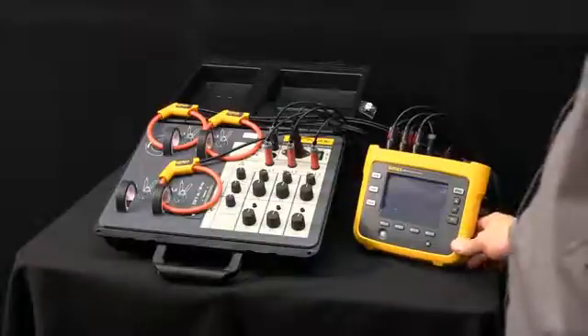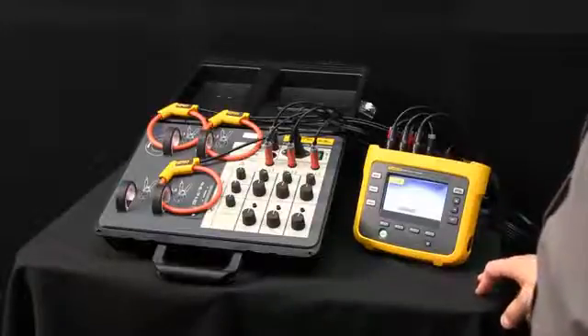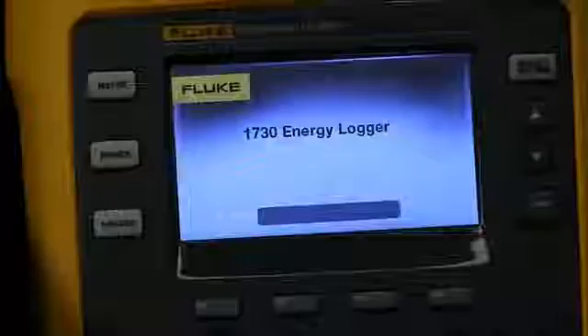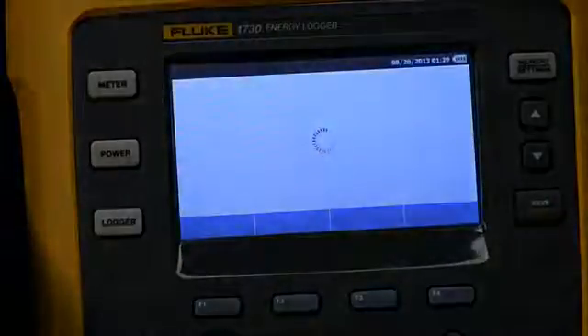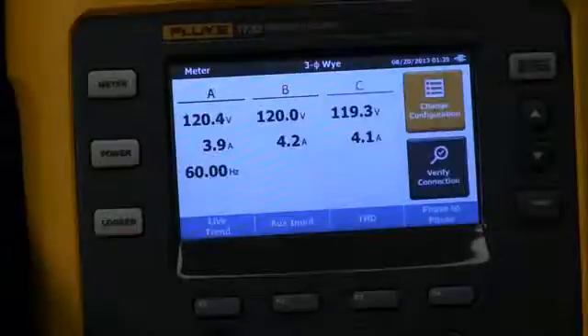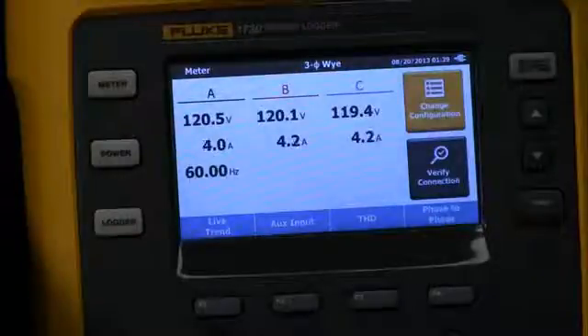Once the connections are made, let's go ahead and power the unit on. Whether we got our connections hooked up properly, we'll be able to identify that when the logger powers on and one of the screens will show us that we've got all of our CTs turned the right direction whereas all the arrows should be facing towards the load or maybe we've got something mixed up.